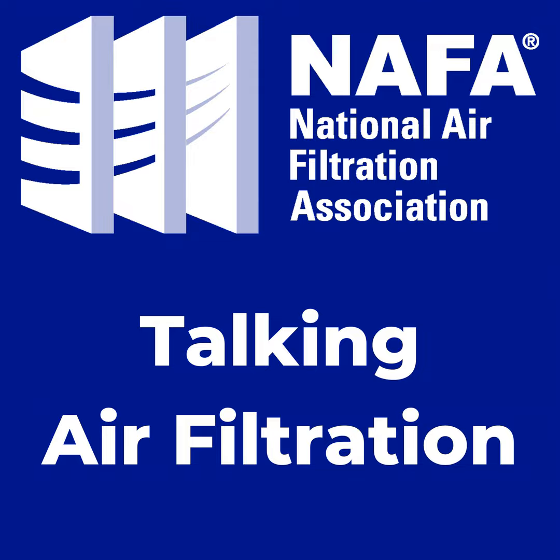So it's really about finding that balance between what's going on in the filter and the mechanics, and trying to get a better benefit of everything that you're looking at. The reason for this, reiterating it, is that these mechanical filter media like microglass have a depth loading region, so you can see the dust load sieve through the filter media, and the membrane is kind of just like a wall. It's just face loading it, and then you're going to have an increase in pressure drop based on that.